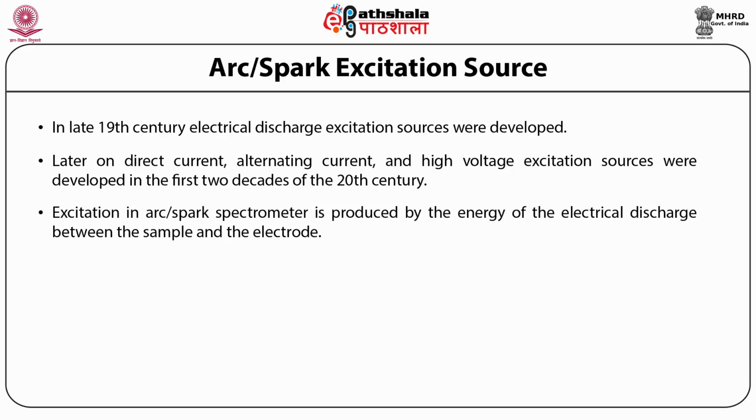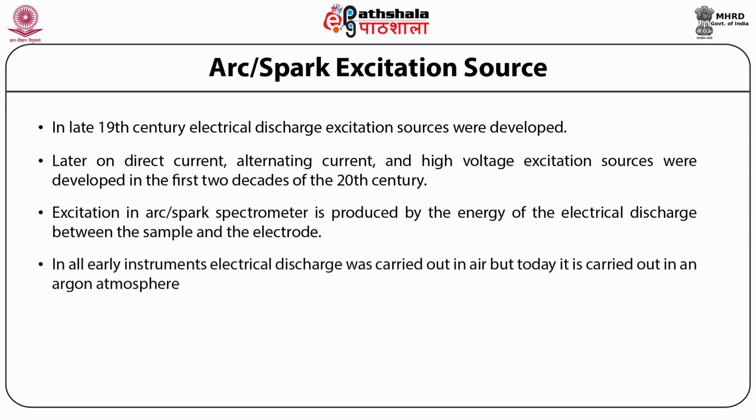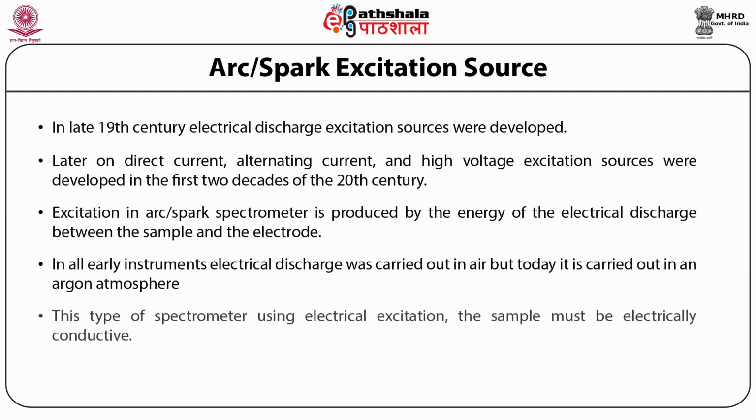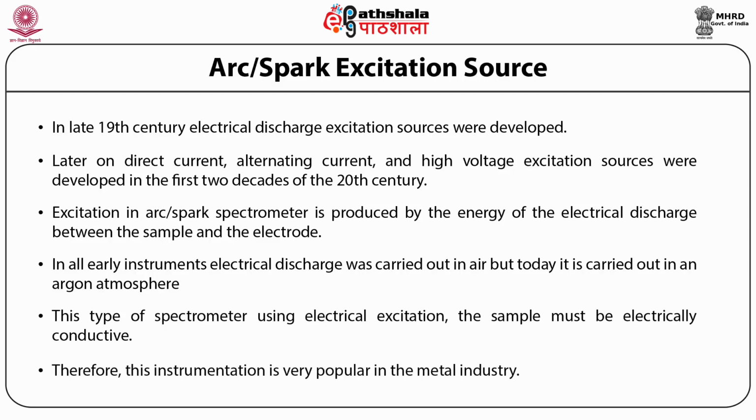and the electrode. In all early instruments, electrical discharge was carried out in air, but today it is carried out in an argon atmosphere. For this type of spectrometer, using electrical excitation, the sample must be electrically conductive. Therefore, this instrumentation is very popular in the metal industry.